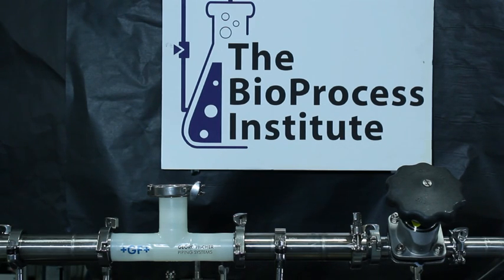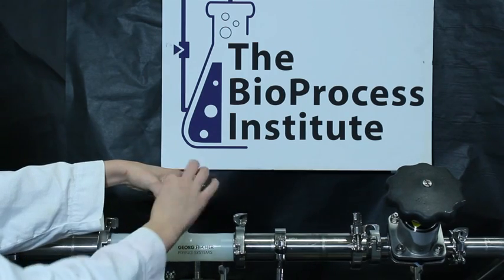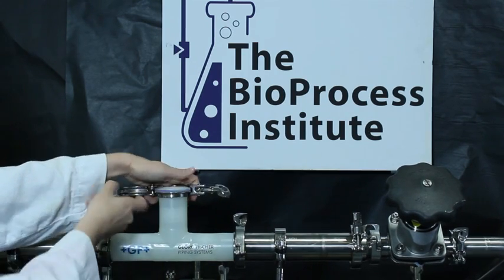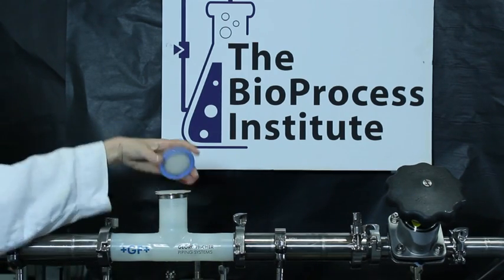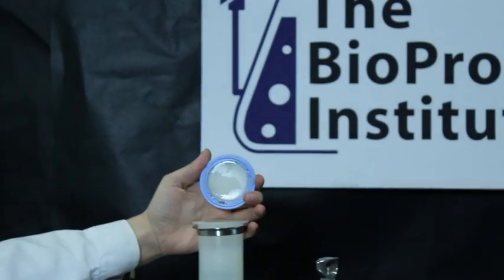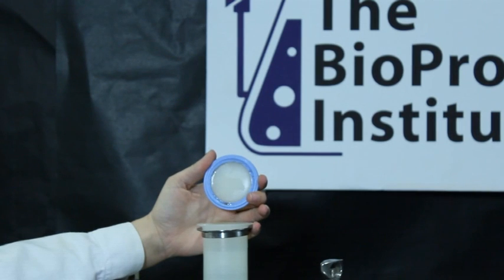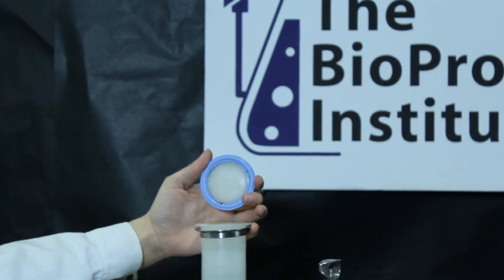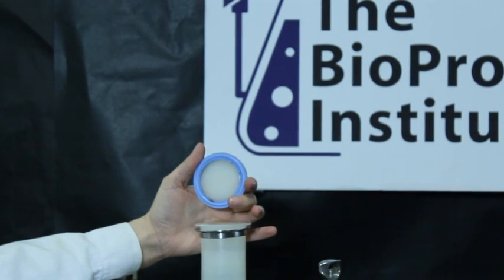After approximately 5 minutes of the pump on let's remove our end cap and see how clean it is. As you can see the amount of grape juice has been reduced but not completely eliminated after 5 minutes and a velocity of 5 feet per second.